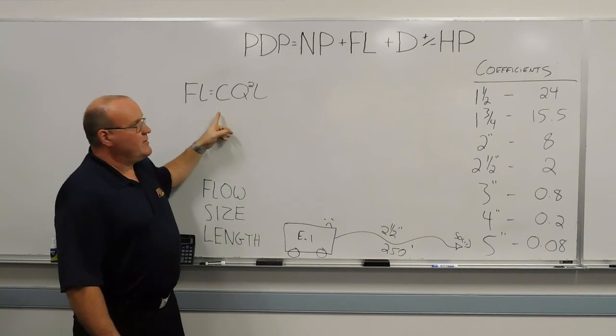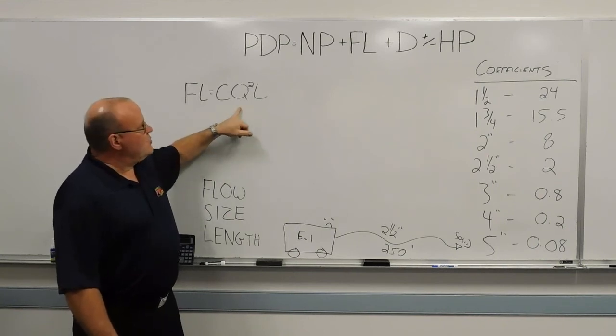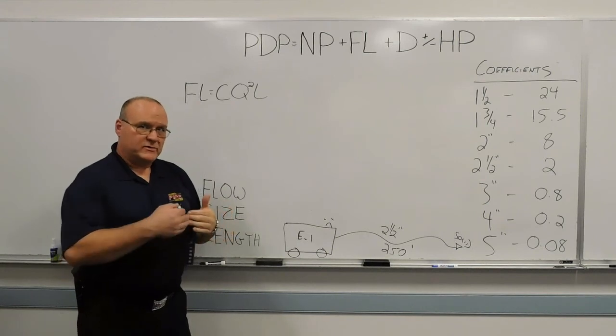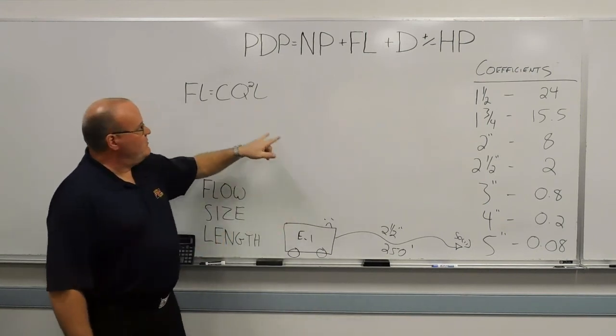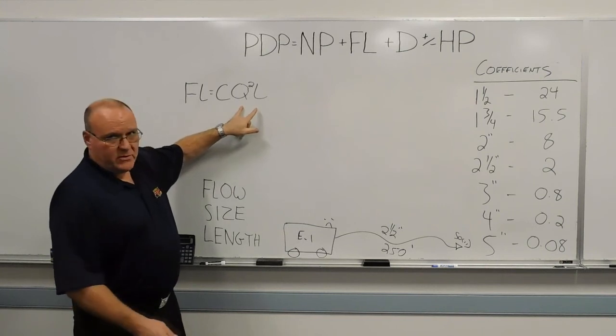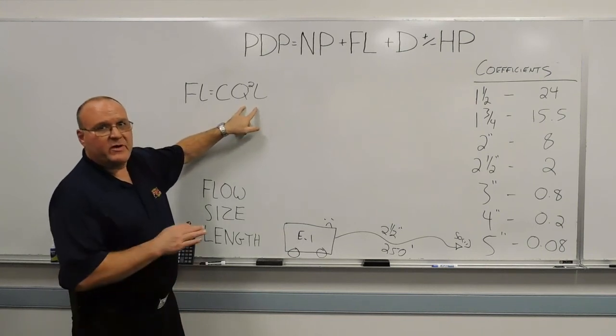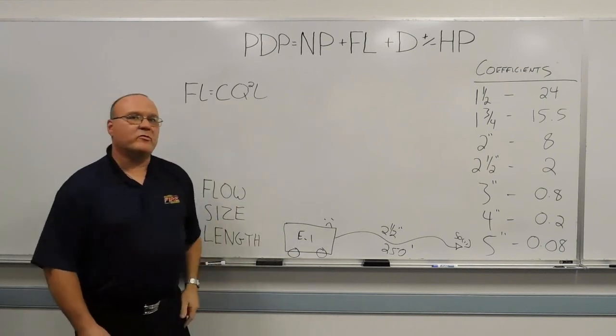The C is the coefficient. The Q² is your gallon per minute flow, squared. And then your L is your length of hose. And both the flow, or the Q, and the L are divided by 100 before they're multiplied in that formula.